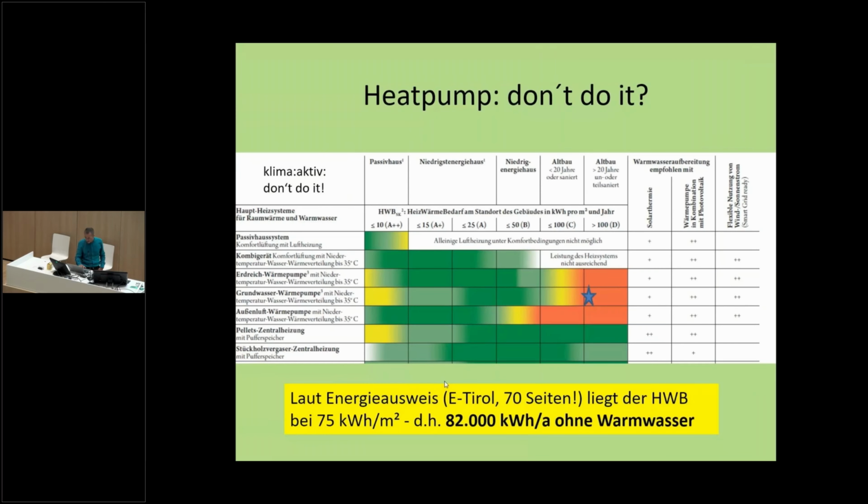Here there was the official scheme, and they said don't do it, because there's too big a heat demand, and we have radiators and no floor heatings. And we tried it without being sure that it will work. I had one measurement, data logging in 2 flats, and I saw, okay, it could work.